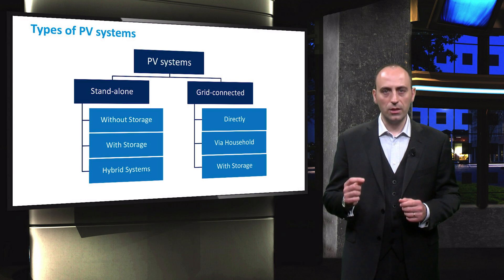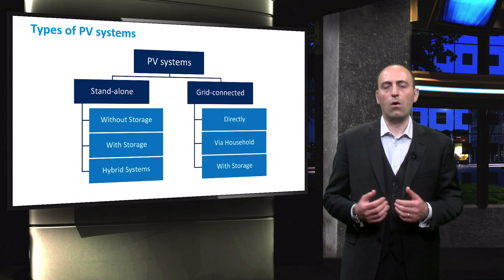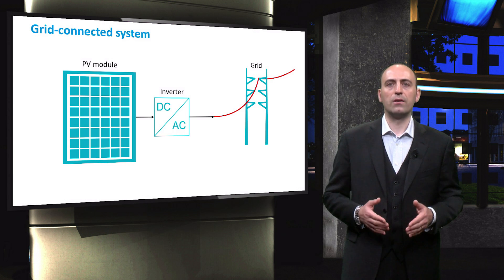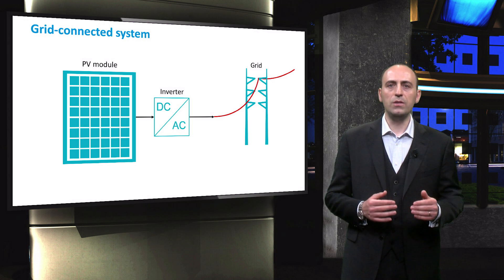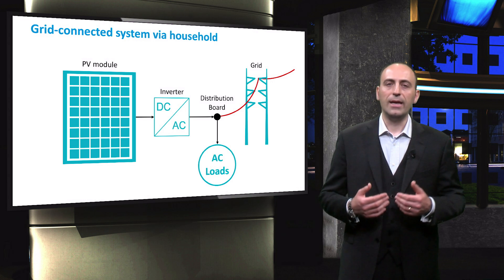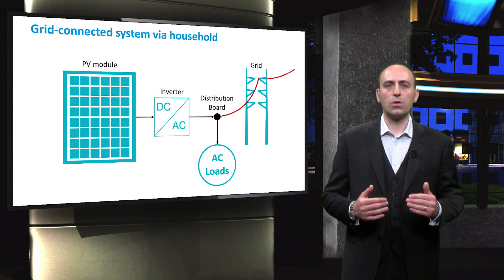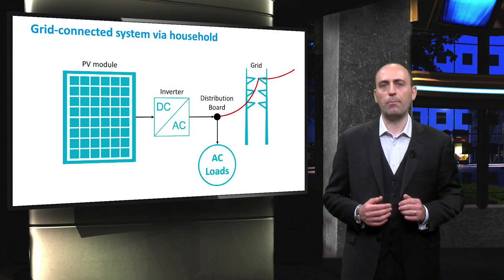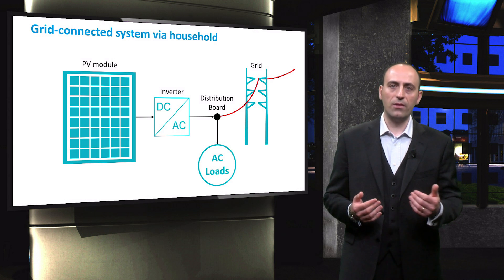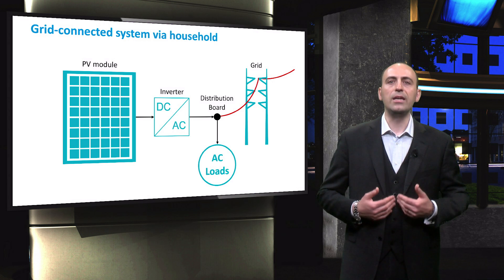Let's now move to the second group of PV systems, the grid-connected ones. Grid-connected systems are typically used in buildings. They can be connected to the grid directly or via a household inverter, and might also include storage, as we shall see in next slides. In the simplest version, PV modules are directly connected to the grid via an inverter, which converts the DC power coming from the modules into AC power for the grid at 230V and 50Hz in Europe. In case of small systems such as those installed in households, the inverter is connected to the distribution board. This device transfers the generated power into the electricity grid or to AC appliances in the house. In this way, the grid acts as a buffer into which an oversupply of PV electricity is transported and redirected to other loads. These systems do not require batteries, and the grid supplies the house with electricity in times of insufficient PV generation.